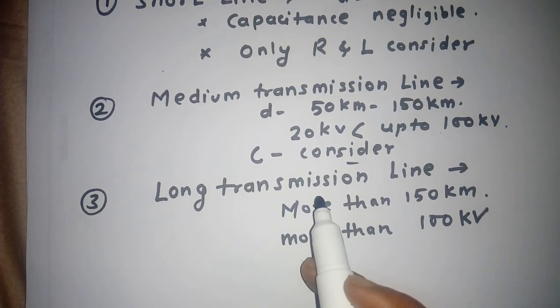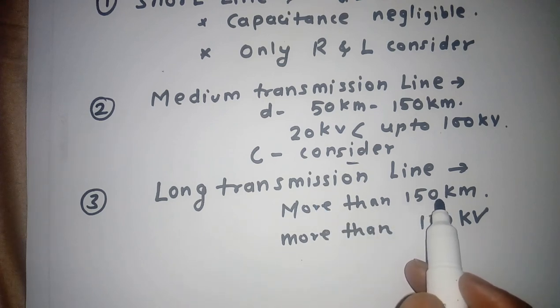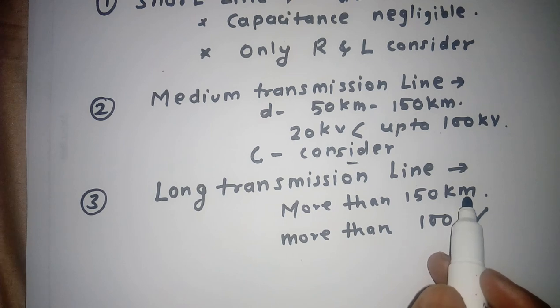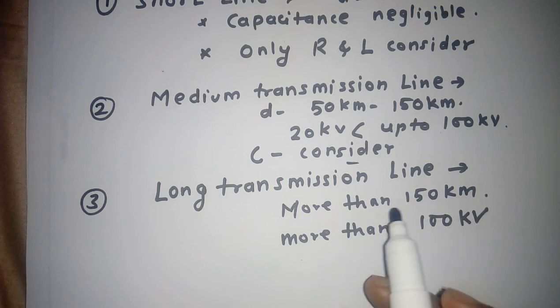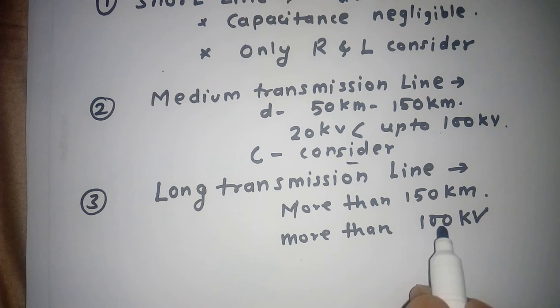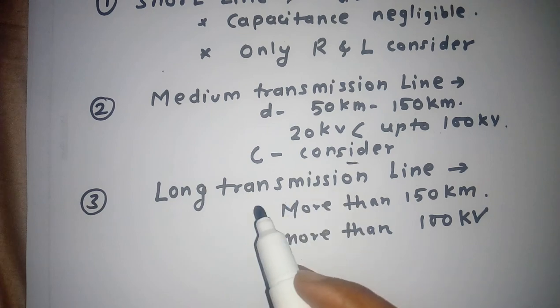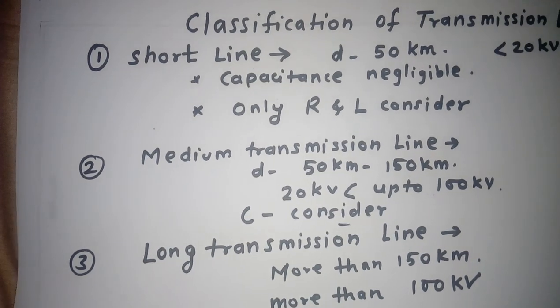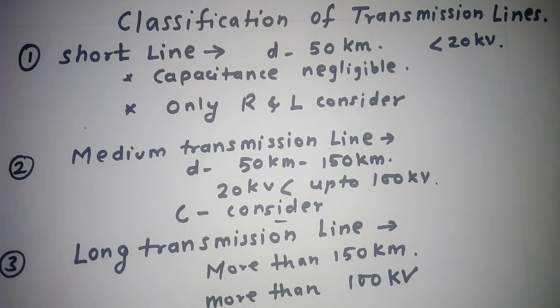The third type is called the long transmission line. Its length is more than 150 kilometers, and any line with more than 150 kilometers in length and more than 100 kilovolts in voltage level is classified as a long transmission line. This is all about the classification of transmission lines. Thank you very much.